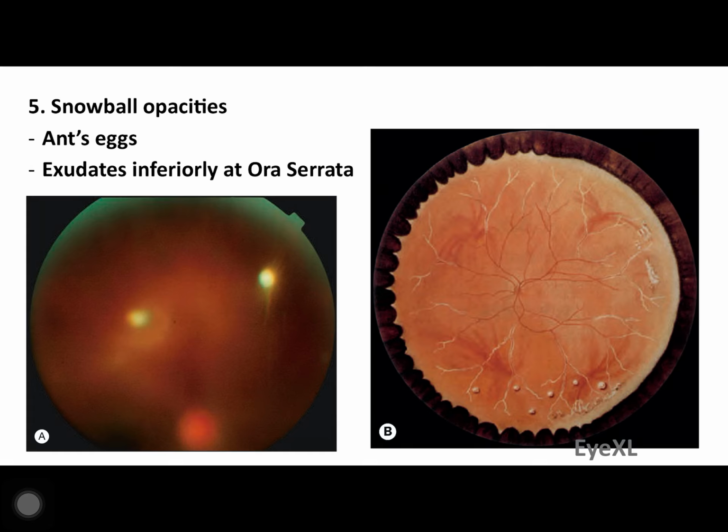So the bottom left image is most likely an image which is taken on an indirect ophthalmoscope. The indirect ophthalmoscope is that head mounted instrument that we use. Why do I call it indirect? Because the opacities are seen superiorly in the image, whereas they are more commonly present inferiorly. Understand, in an indirect ophthalmoscope, the image is rotated laterally as well as superior inferiorly because of the lens that we use, because of the optics of the indirect ophthalmoscope. Whatever I see superiorly is actually present inferiorly.